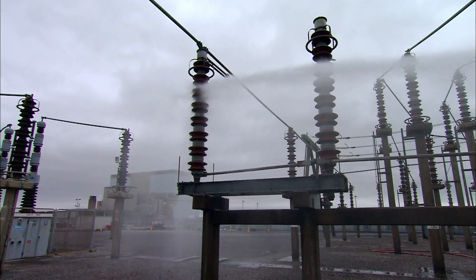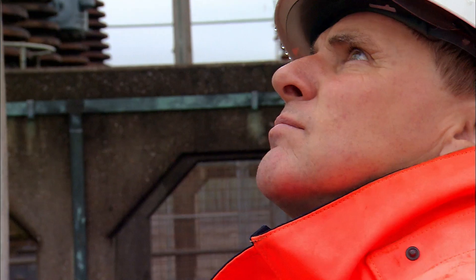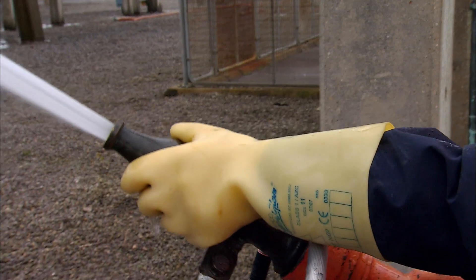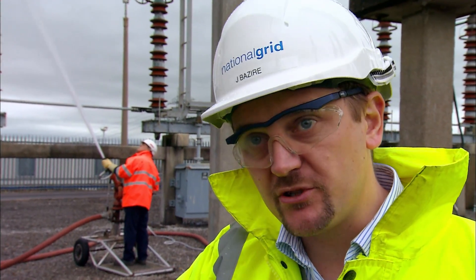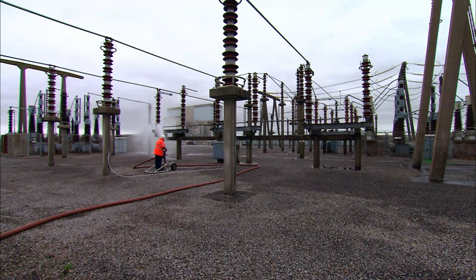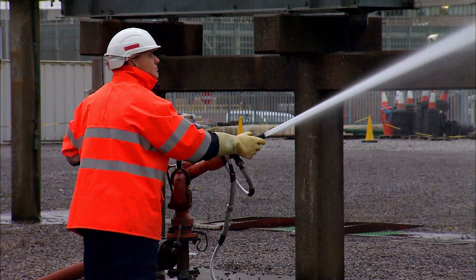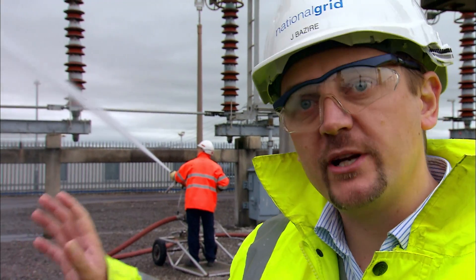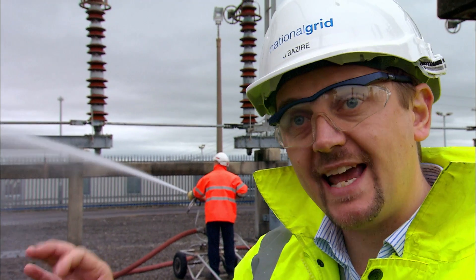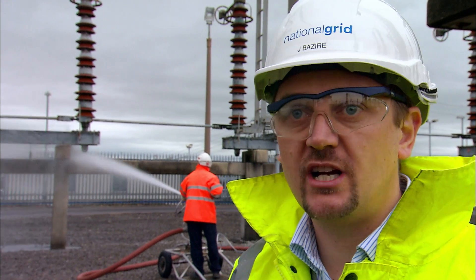The wash appears safely underway, but conditions can change unexpectedly. The conductivity of the water is constantly monitored. If the conductivity — that is, the purity of the water — falls below a certain level and it becomes too conductive, the procedure stops. There's a 15-second timeframe: an alarm sounds, washing stops, and the pumps shut down automatically. In addition, the pressure at which the water is delivered at 80 PSI must be maintained — if that drops off, the whole system will shut down.